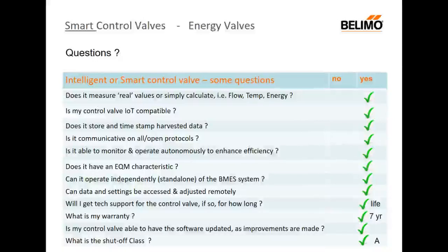We considered some points about the mechanical, perhaps the electrical smart valves we should as well. So let's ask, does it measure real values or just calculate them? Because that's important. I think measured value, if you want to control something, measuring it's probably the best way. Is my control valve IoT compatible? Because I may want to connect it to other systems in the building. Does it store and timestamp the data that it draws off the system?